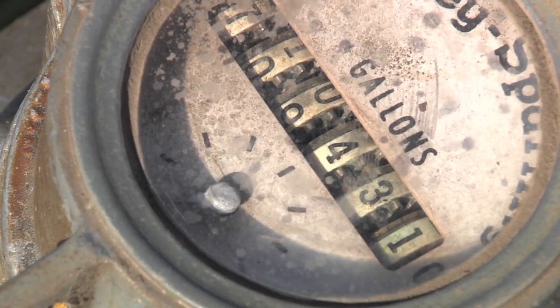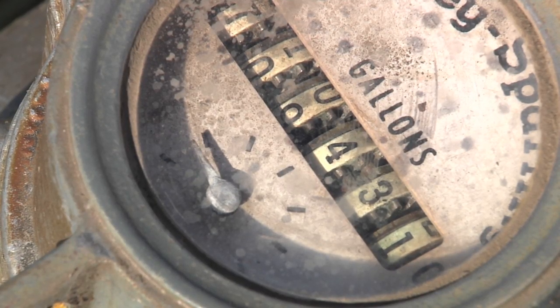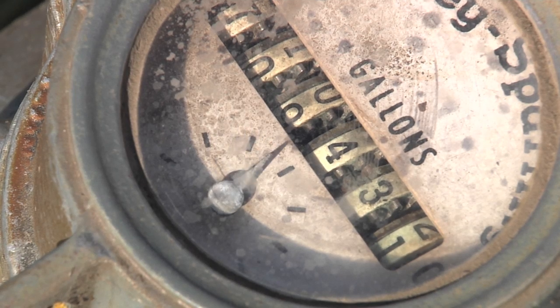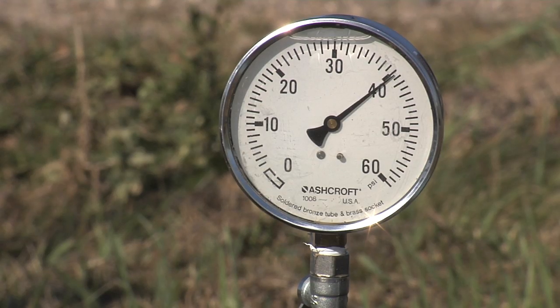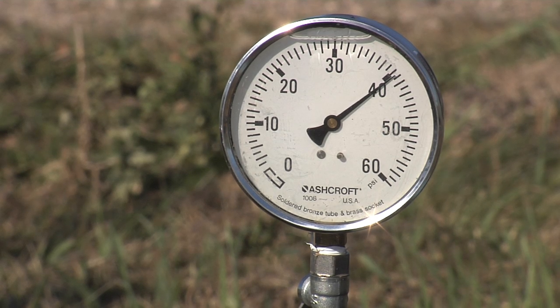Well, now that we've completed the pump efficiency test, a farmer can always do their own. Really, all he needs is a good, working, accurate flow meter and a good, accurate pressure gauge. Now this one is relatively new. This reads pretty good. When we compared it against our readings, they were identical.